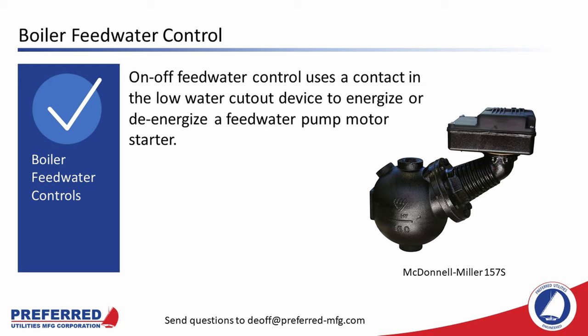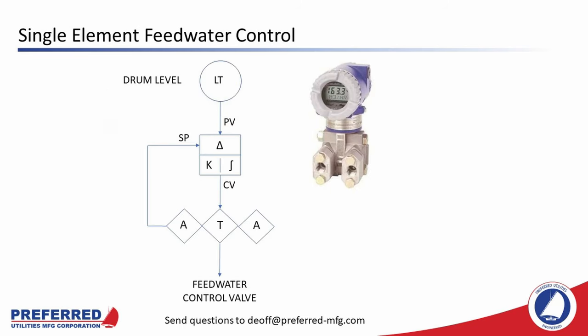On-off feedwater control uses a contact in the low-water cutout device to energize or de-energize a feedwater pump motor starter — the most common device being a McDonnell Miller 157S, with one switch to shut off the boiler on low water and another switch set slightly higher to toggle the feedwater pump on and off. Single-element drum level control uses a drum level signal — usually a 4 to 20 milliamp analog signal from a differential pressure transmitter mounted on the boiler. The controller will be a true PID controller, or on smaller boilers a proportional-only controller that sends a 4 to 20 milliamp output to a feedwater control valve. Preferred likes to use ball valves or characterized seat ball valves with a more linear characteristic. This system offers more precise drum level control than on-off control, plus auto-manual capability and the ability to change water level set points.